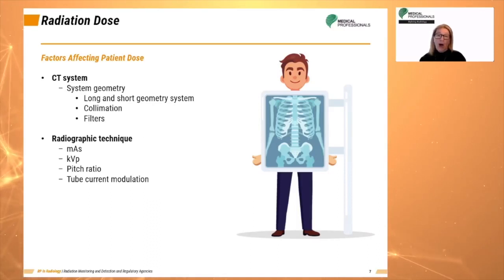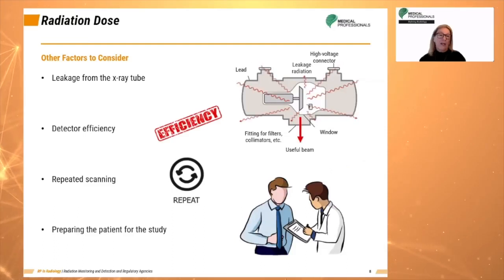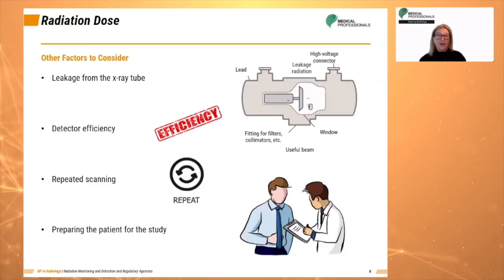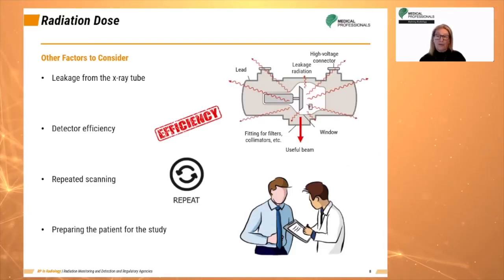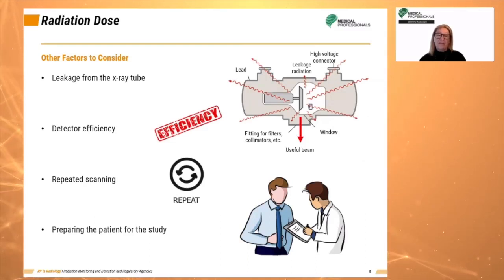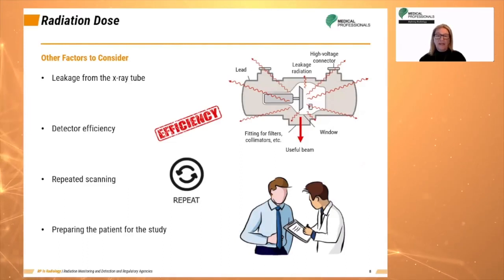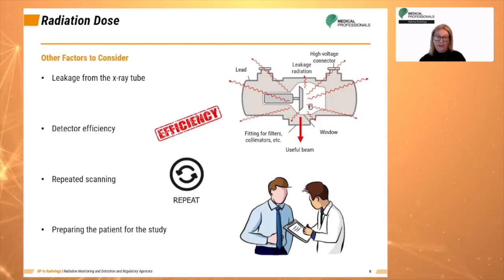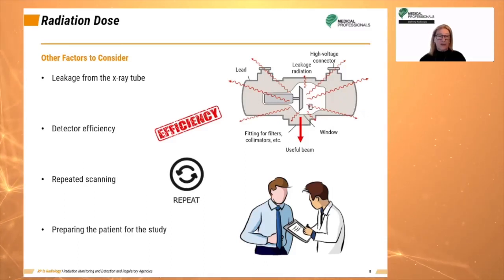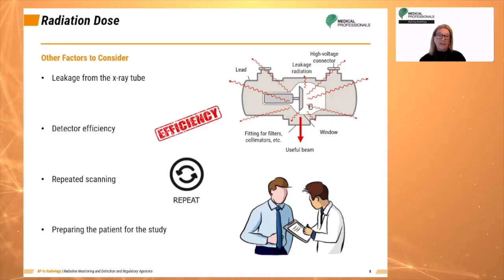Tube current modulation is similar to automatic exposure control used in CR and DR radiography. Other factors to consider include leakage from the x-ray tube — the scanner should be checked and maintained regularly. Checking detector efficiency makes better use of radiation passing through the patient. Repeated scanning due to improper protocol choice should be avoided, and preparing the patient for the study decreases skepticism and increases cooperation.